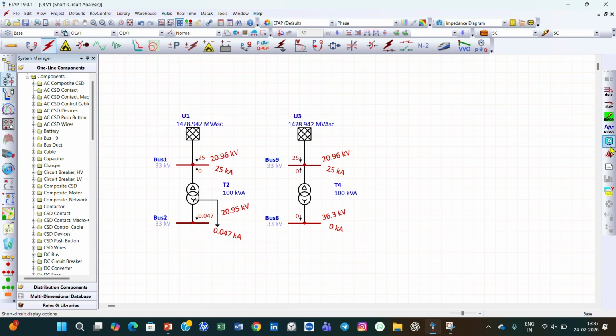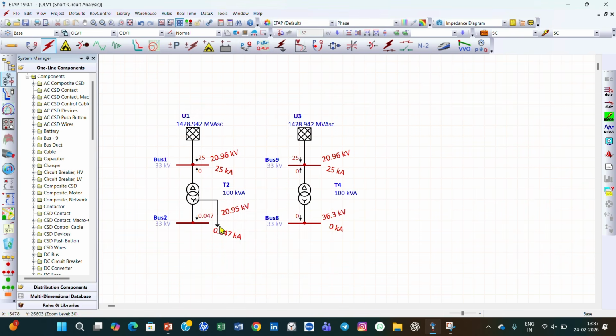Now you can see, we can go to the display options and we have selected the single line to ground fault here. You can see in the single line to ground fault the current is 0.047 kiloamperes here. This is the single line to ground fault current, and here it is 0. When it is 0, that means the system cannot detect it, the relays cannot detect it, and the system will run under fault condition.